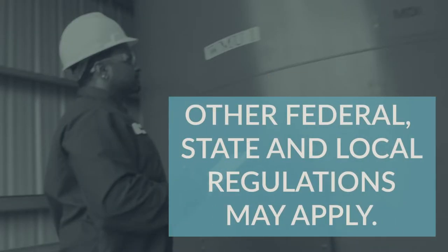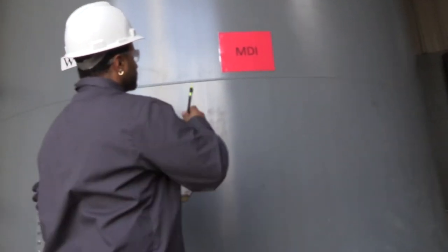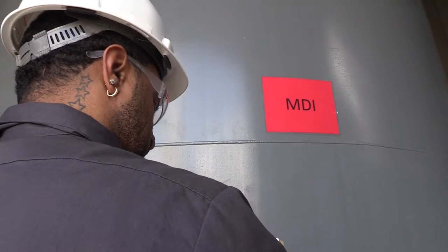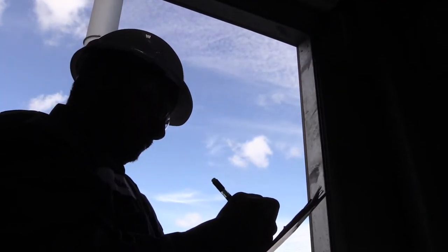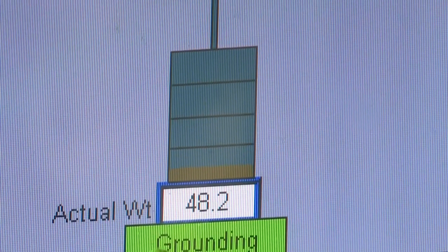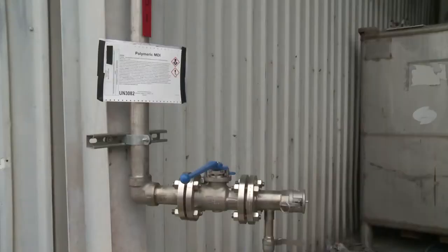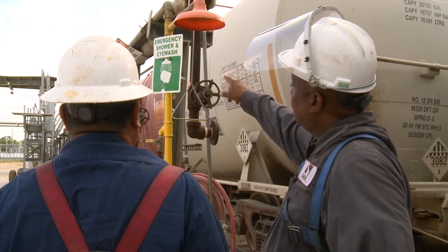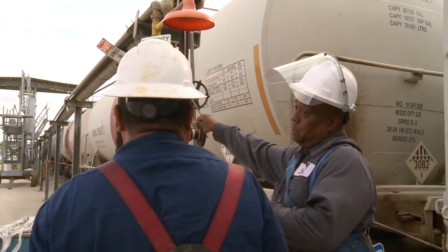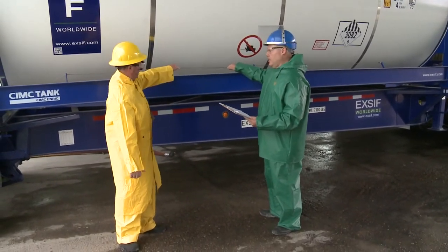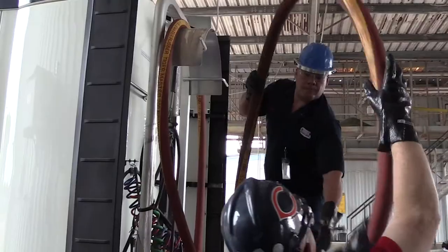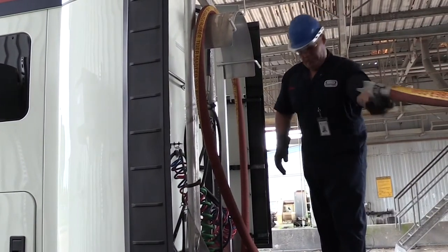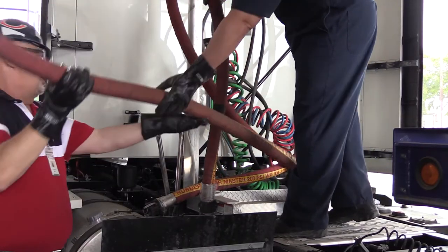The storage and handling of MDI at your facility may be subject to other regulations, so adapt the process as required. Once the paperwork and tank container checks are complete, the next step is to check your own equipment. If the content of the tank container is to be offloaded into a receiving tank, make sure that the tank is the correct one for the product and that there is enough room in the tank to hold this shipment. Clearly identify the unloading connection on the receiving line. The unloading operator will show the driver the location of the nearest eyewash station and safety shower. The driver will show the operator where the container's remote emergency shutoff is located. Transfer hoses for MDI products are typically 2 inches in diameter to differentiate them from the 3-inch diameter hoses and fittings generally used for polyol or resin products. Hoses may also be color-coded and/or labeled to assist in eliminating transfer errors.